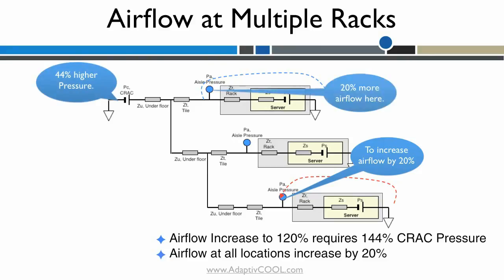But all the locations in the data center, not just the third rack, receives 20% higher air flow. That means the first rack is now excessively over cooled, but the third rack is just about in thermal control.